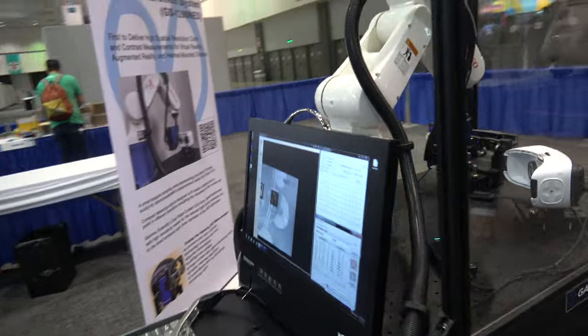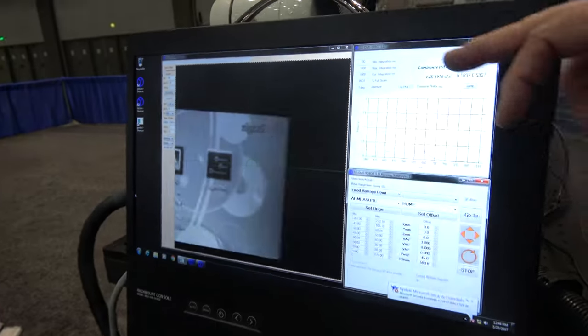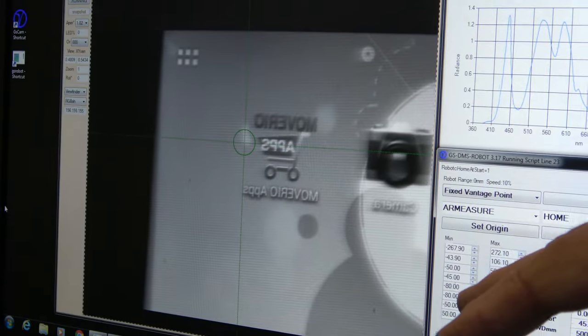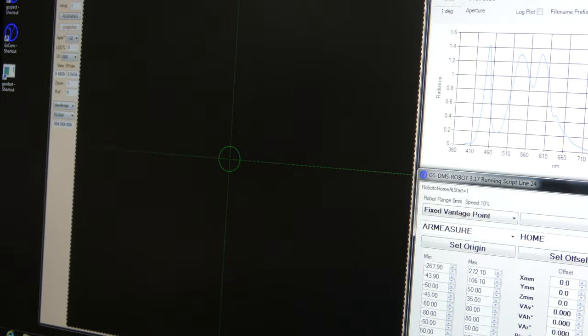On the screen here we have an internal 8.9 megapixel camera image. We can do image quality analysis in terms of MTF, depth of contrast, as well as the uniformity of the spectroradiometric measurement made in the center — about a one degree aperture in a seven by seven degree field of view. The spectroradiometric data shows the light measurement made right there.